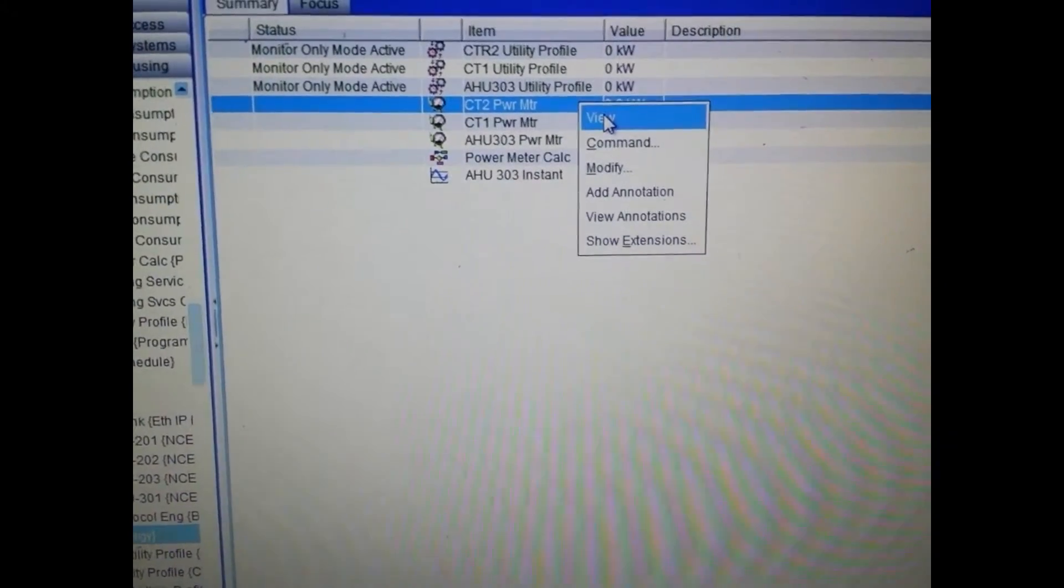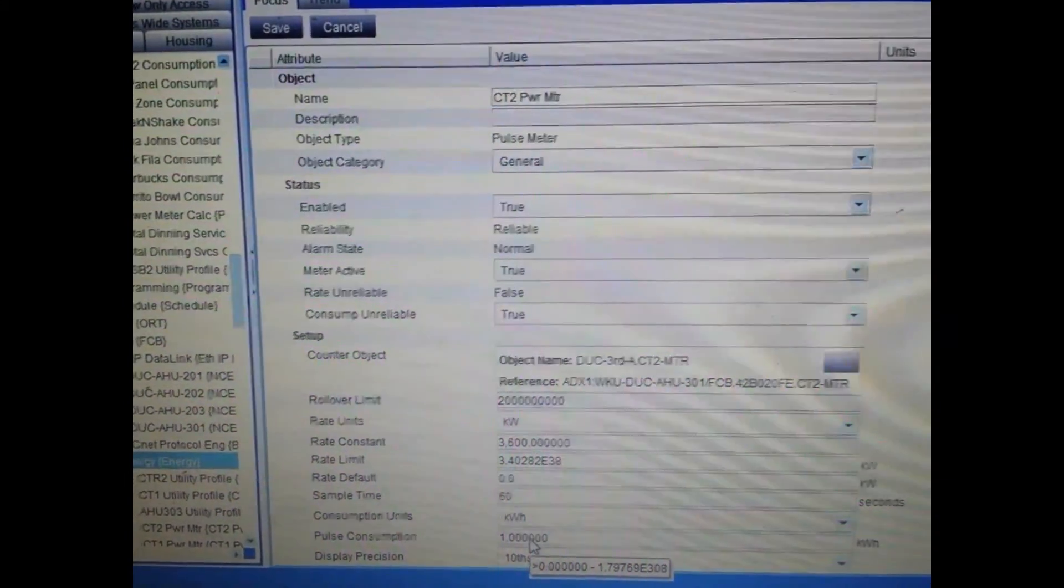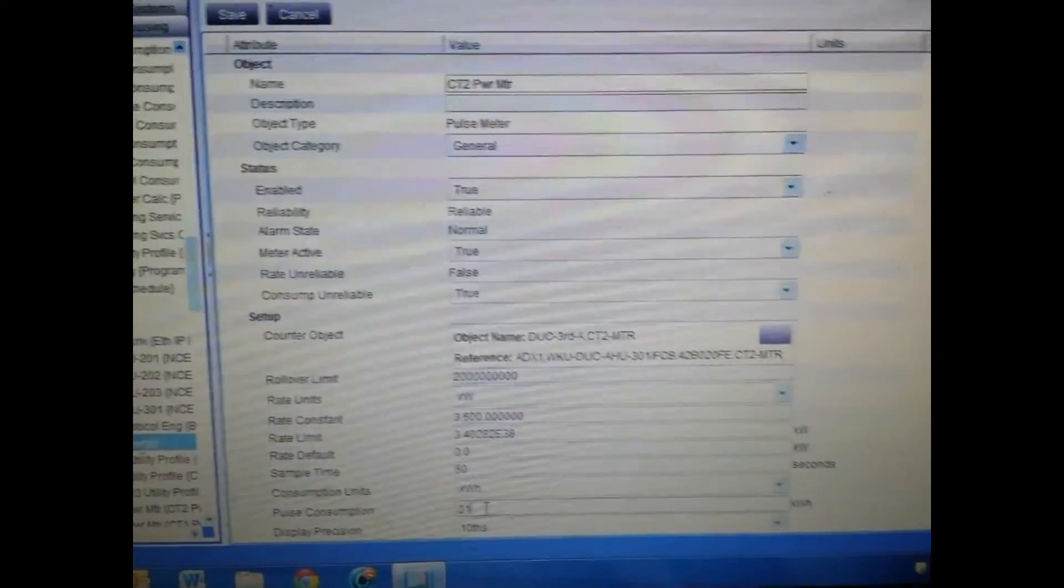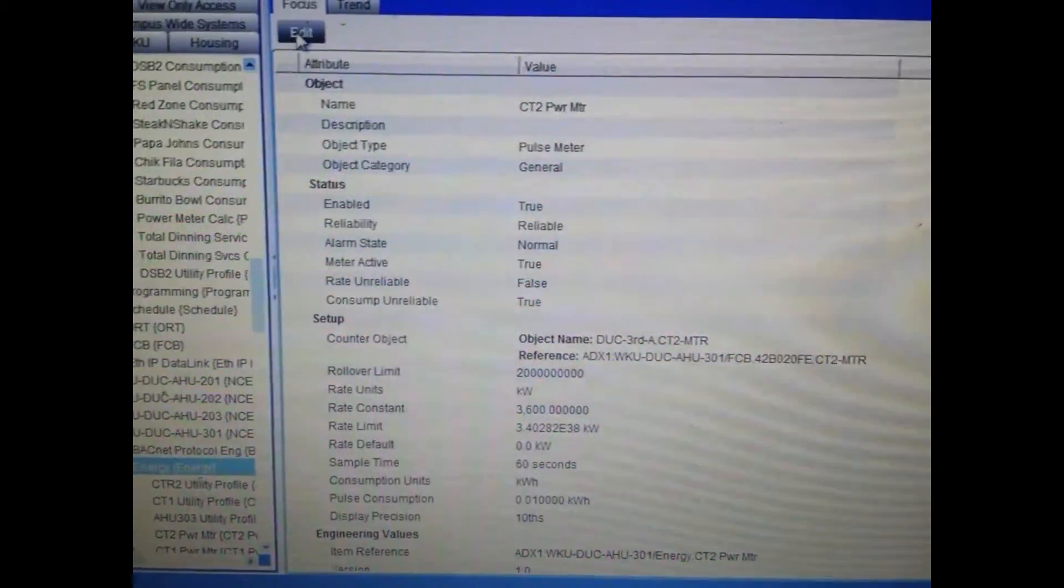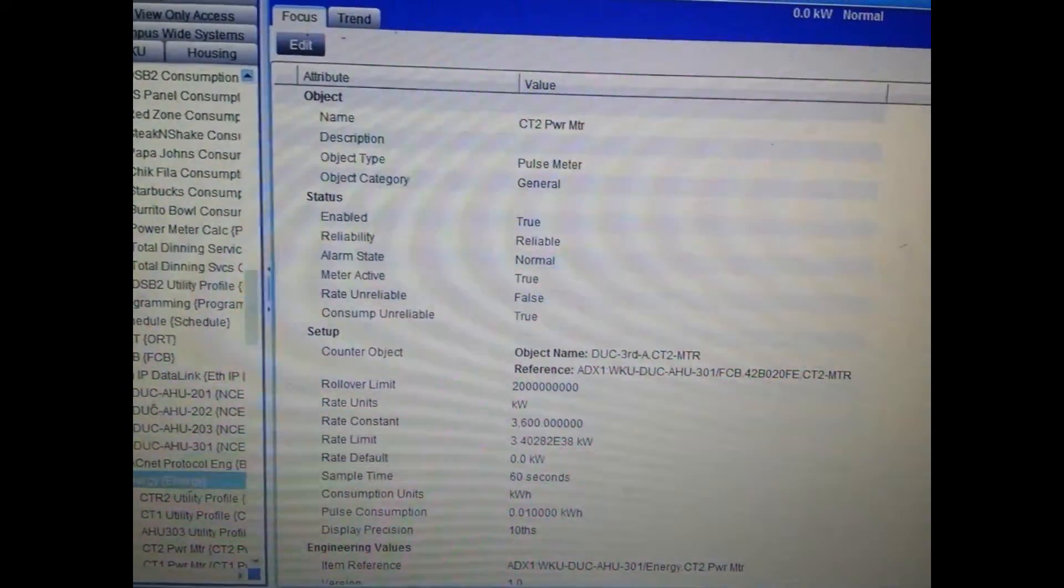Now then, within the Metasys extended architecture system, we have to adjust the resolution in there as well. So I'm going to go into the meter and press edit. The resolution point that I need to change right now is pulse consumption. Right now it is at 1 kWh. I need to change that to match what we have now entered in the meter. So I simply highlight it, delete out the old one, enter 0.01, and then hit save. Once I do that, after a short period of time we should start reading the correct consumption from that meter.